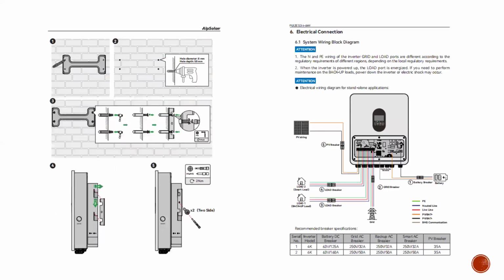So the next thing I would like to talk about is the electrical connection of the system. As you can see in the diagram, the PV has its own breaker to the PV input port. The smart load has its own breaker to the load two port separately. Same thing with load one, which is the critical load, has its own breaker separately. We do not make the mistake of paralleling the load one port, which is your critical load, and your load two port, which is your smart load. Even while you are paralleling the system, you do not parallel the smart load port. The smart load port has to work independently. If you want to parallel three units of an inverter together, you parallel only the load one port, which is the critical port, alone. That is why you see that they have a separate breaker in this diagram.